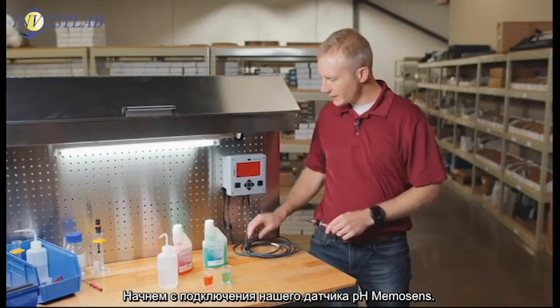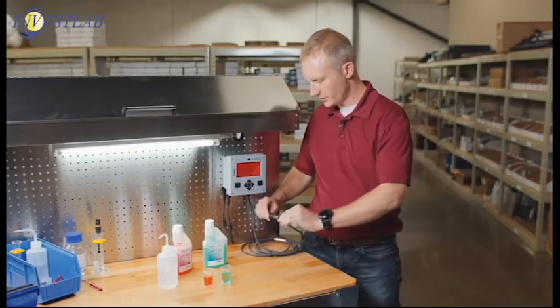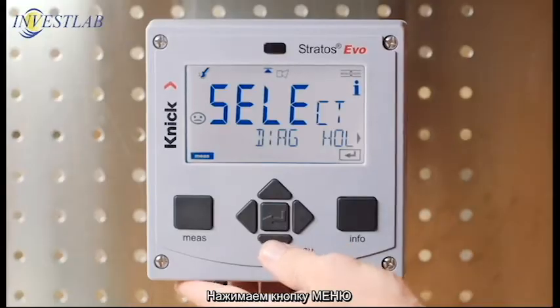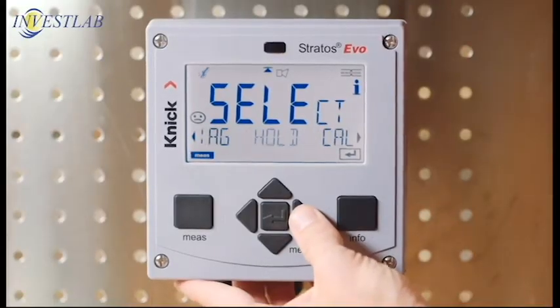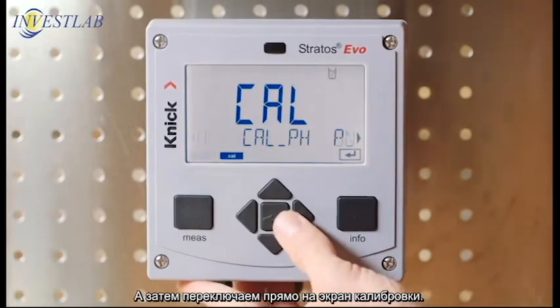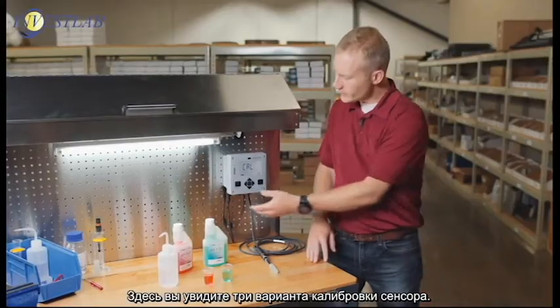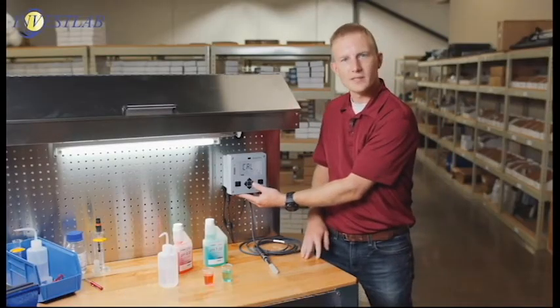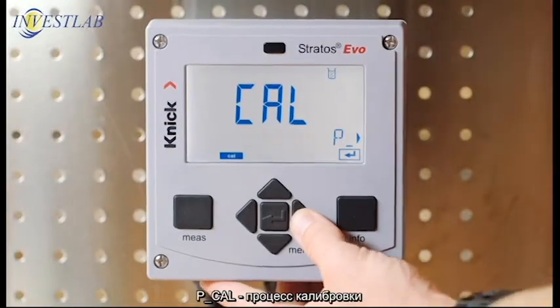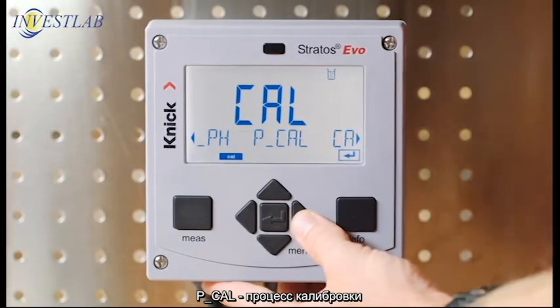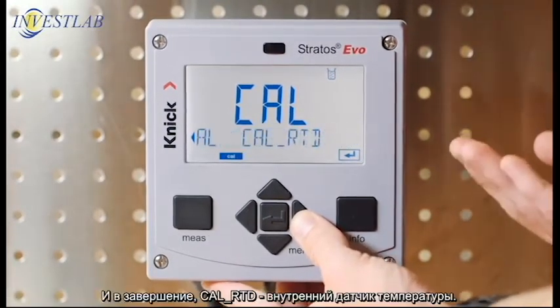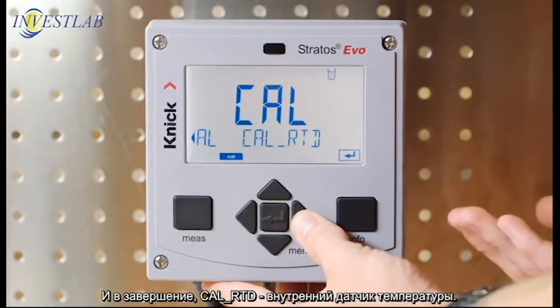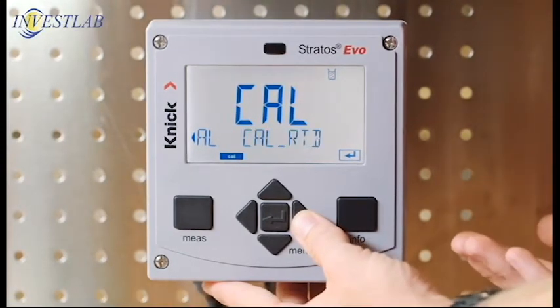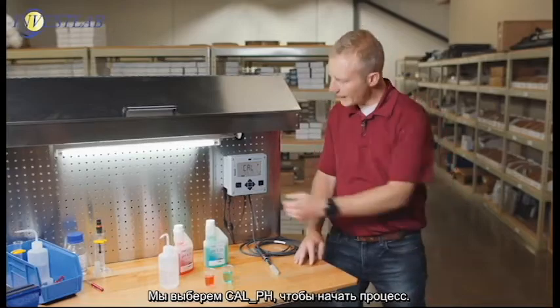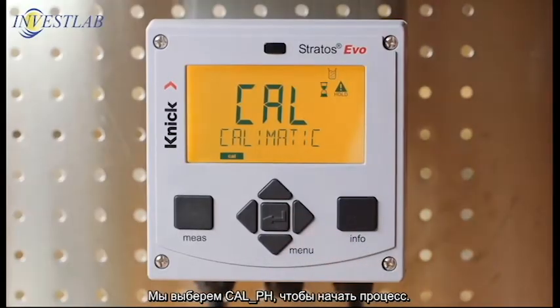Let's begin by connecting our Memosens pH sensor, pressing the menu button, and then toggling right to the calibration screen. Here you will see our 3 options for calibrating the sensor: Cal pH, PCal or process calibration, and finally Cal RTD or calibration of the internal temperature detector. We will select Cal pH to begin the process.